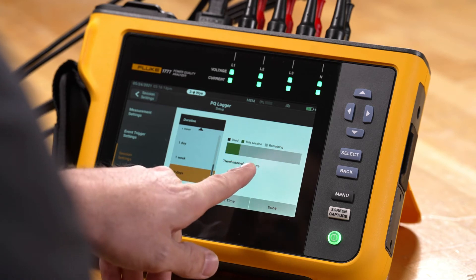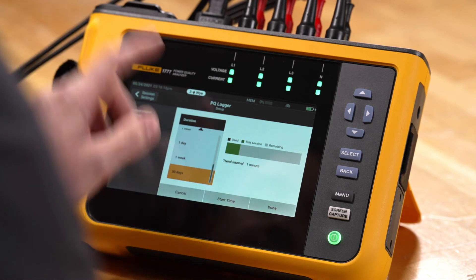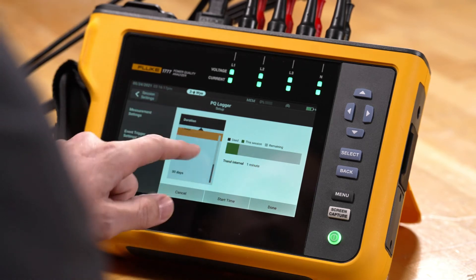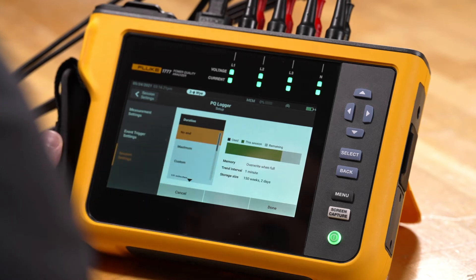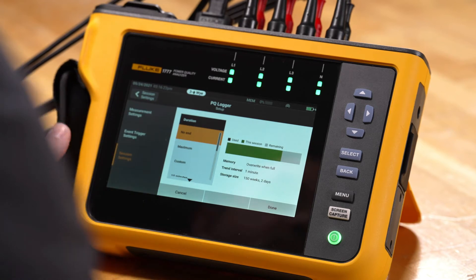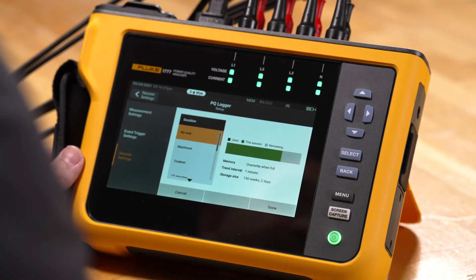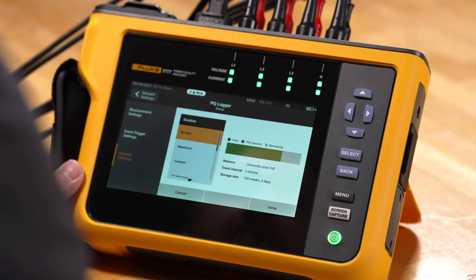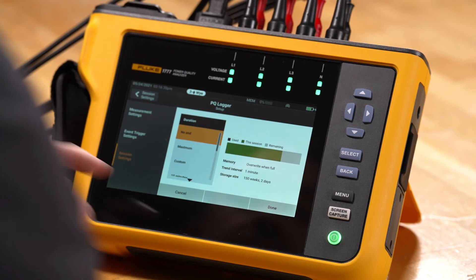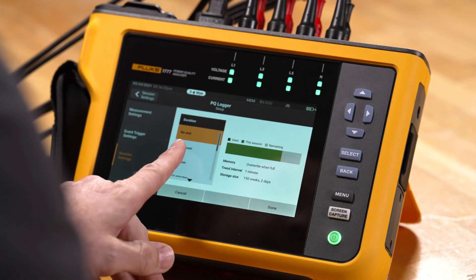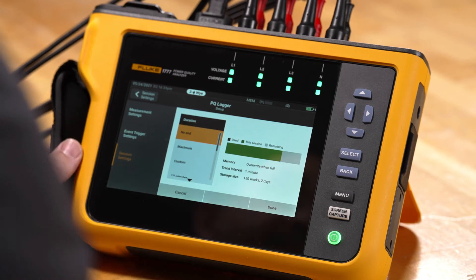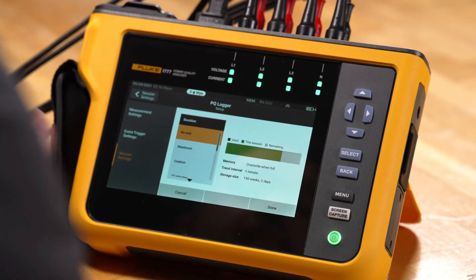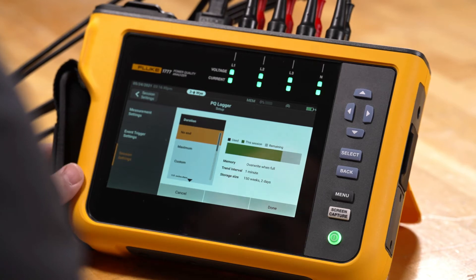We'll see what our current trend interval is, which is one minute. In the duration settings we also have the ability to set it to what we call 'No End.' No End essentially allows us to record limitlessly until the memory fills up, and then it would just overwrite itself. This way, if you need a semi-permanent or permanent recording installation, you can put it into a No End configuration and come back when you need data after an event has occurred.